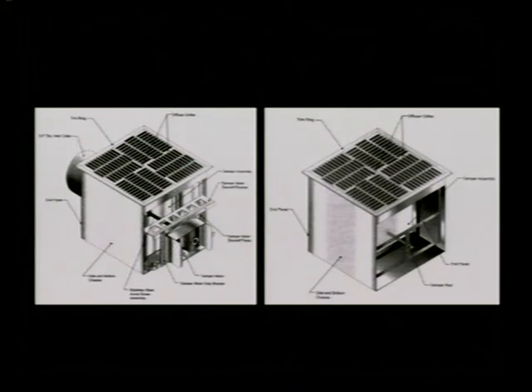This is a picture of the boxes. I probably should have shown that first. The one on the right is a cooling only box. You can see there's a little worm gear damper rod there that the damper blade runs on, and it literally runs from one side to the other based upon how much air you need. In full cooling, that damper's clear on the upper side, and the box is open, and it'll let out about 150 CFM right out of the floor. And then as the thermostat modulates down because it's overcooling, that damper moves towards the open hole and it reduces the amount of air that it lets out of the floor.